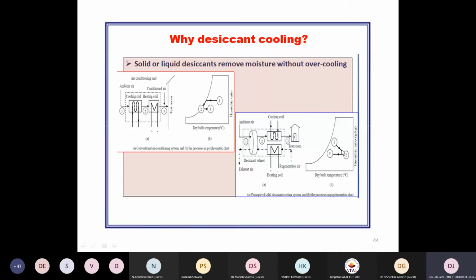The same is represented on the psychrometric chart by the process called 1 to 2, during which you find enthalpy remains constant theoretically, as the process is inclined to be an isenthalpic line, but practically a little variation in enthalpy is found experimentally. Then, after state point 2, we have the process of cooling. The process of cooling is just to remove the delta T needed for comfort. That may be high compared to 4 or 5 degrees in conventional cooling. In the desiccant case, you may find it to be 15 to 18 degrees centigrade. Then it is supplied to the room.